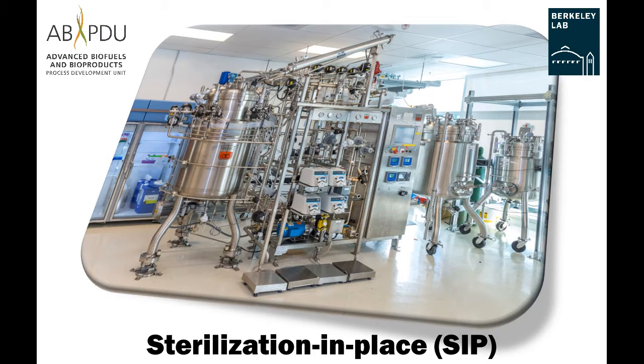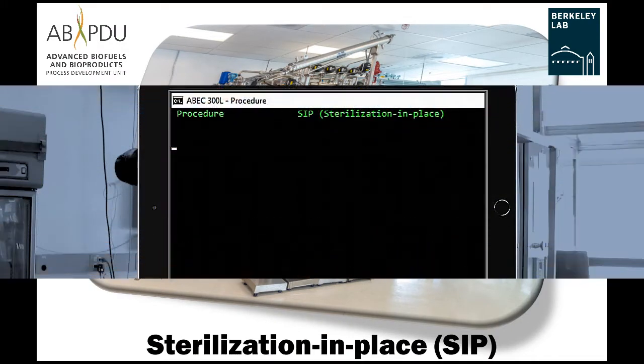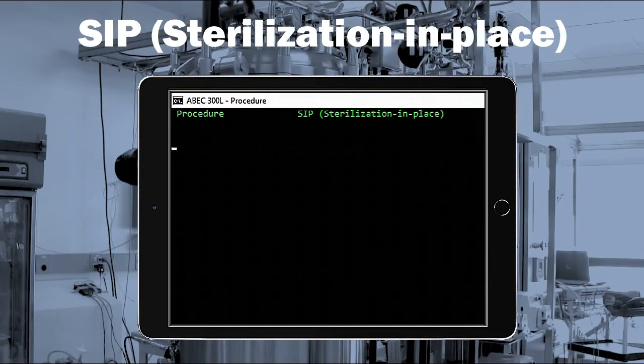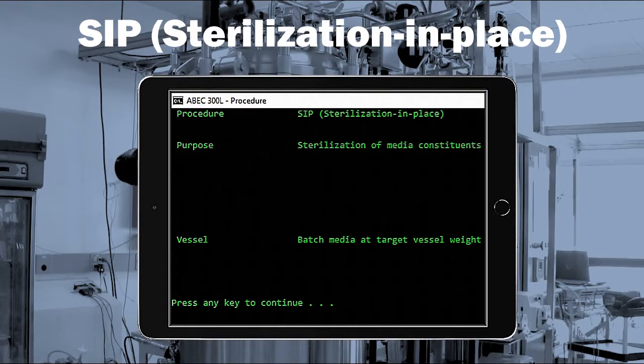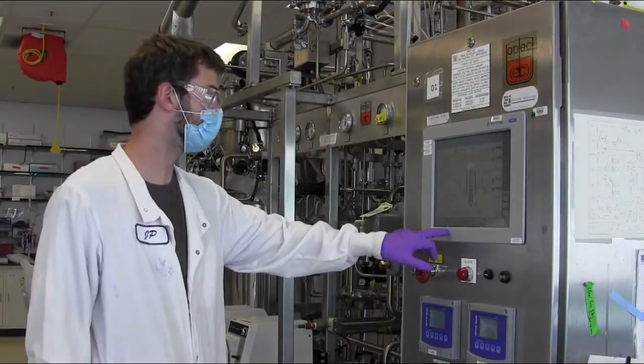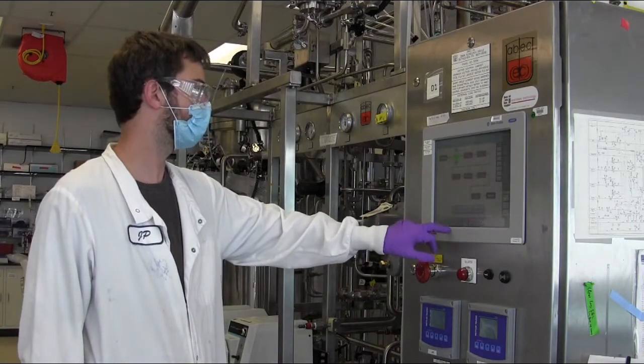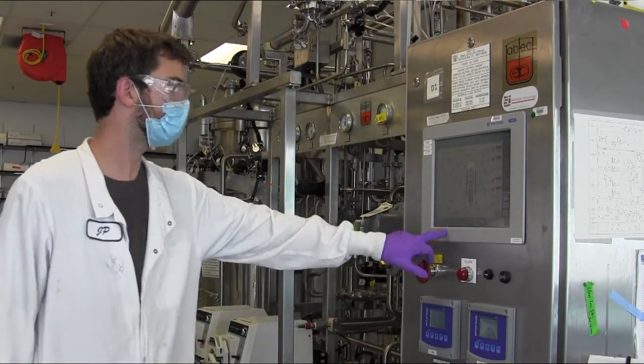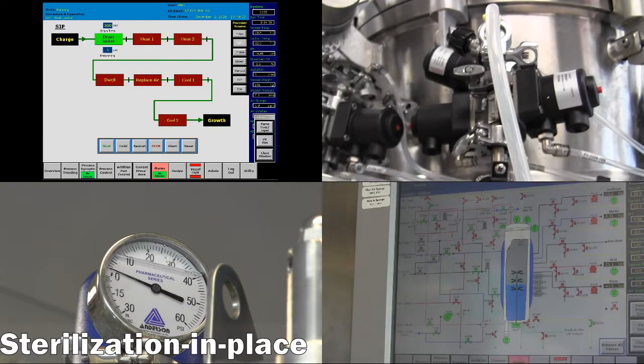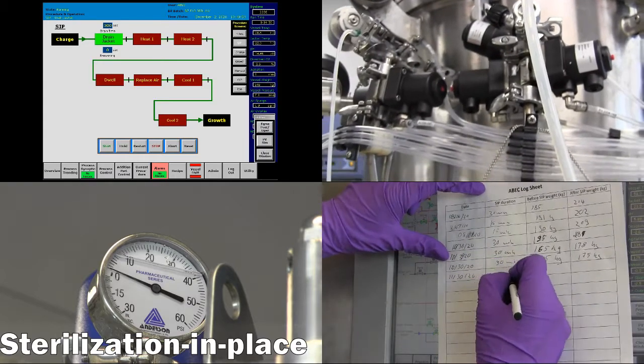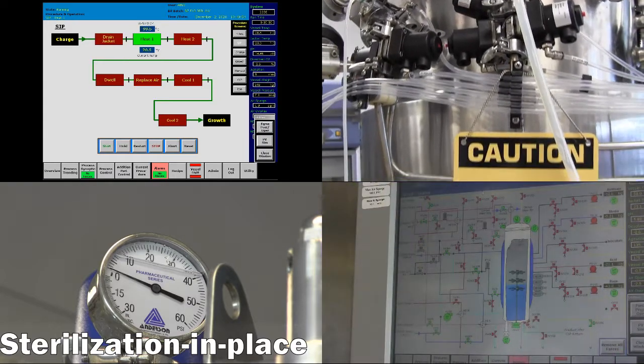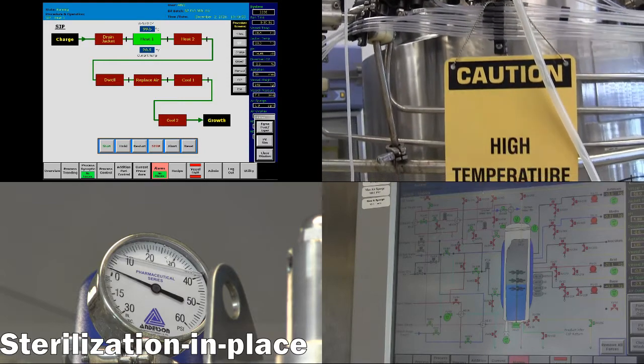Sterilization in place. Once the media components have been batched, the second SIP takes place. This SIP is meant to sterilize the media at the target vessel weight. The SIP procedure is the same. Before starting the procedure, be sure the high pressure and high temperature signage is posted, and record the pre-SIP weight. Again, the vessel will move through 2 heating stages, a dwell period, and 2 cooling phases.